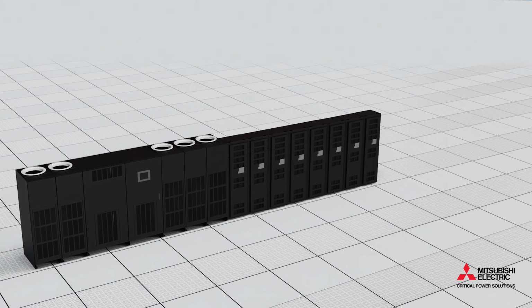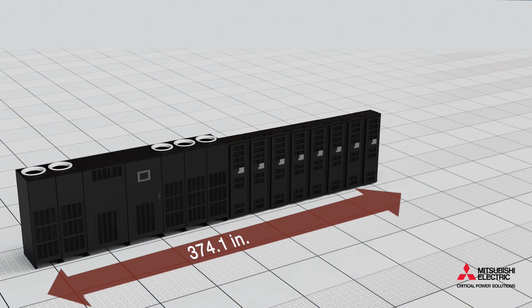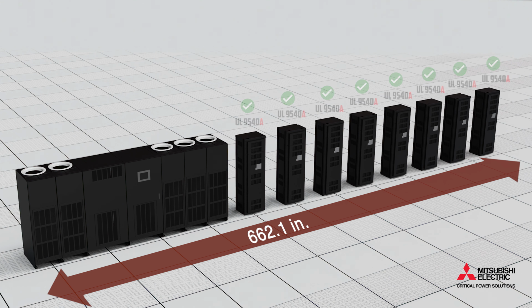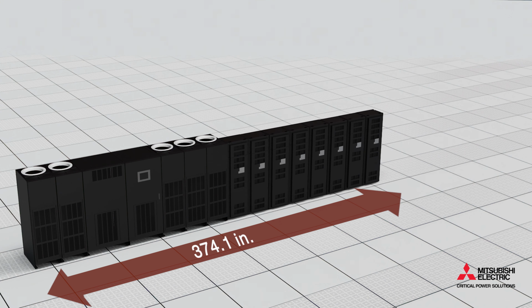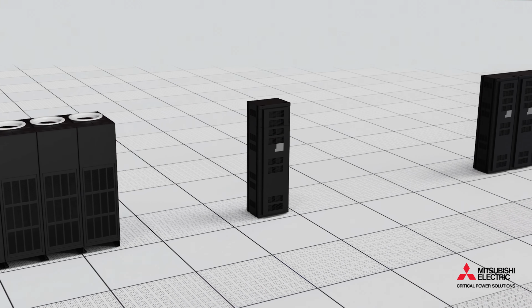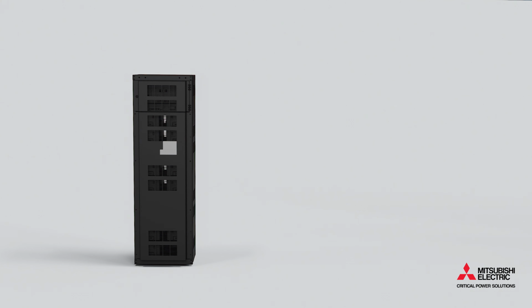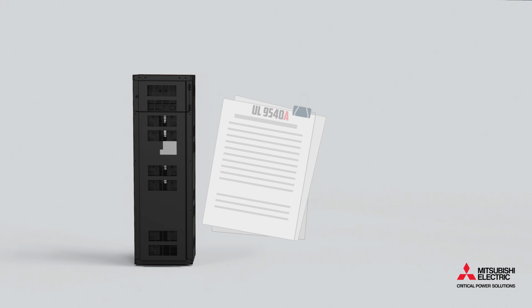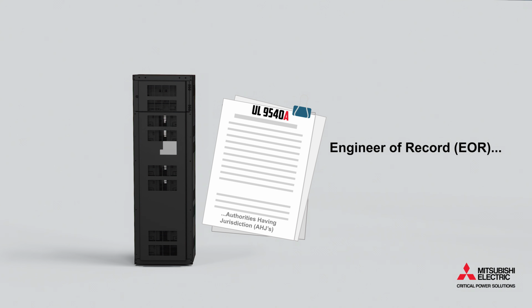Having UL 9540A acceptable results for energy storage systems larger than 50 kWh allows all battery racks or DC technology cabinets to be side by side, taking up less footprint. The DC technology in question must have acceptable UL 9540A test results, and those full test reports must be provided for review to the engineer of record, the EOR, and authorities having jurisdiction, the AHJs.